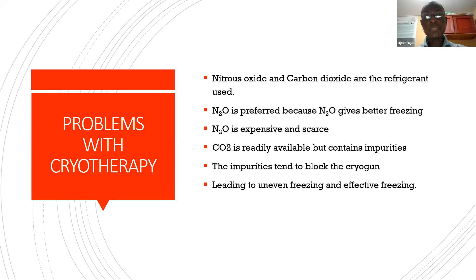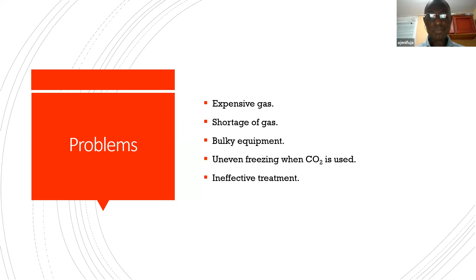The other refrigerant is carbon dioxide, which is readily available but contains a lot of impurities. The impurities tend to block the cryo gun, diminishing the effect of freezing. Because of the blockage of the cryo gun, there is uneven freezing and ineffective freezing of pre-malignant lesions. Gas can be in short supply, and again, the equipment is very bulky and very huge. Sometimes it's difficult to move them from one screening point to the other. Also, the gas in the cylinder may finish suddenly, and that gives a lot of disappointment.